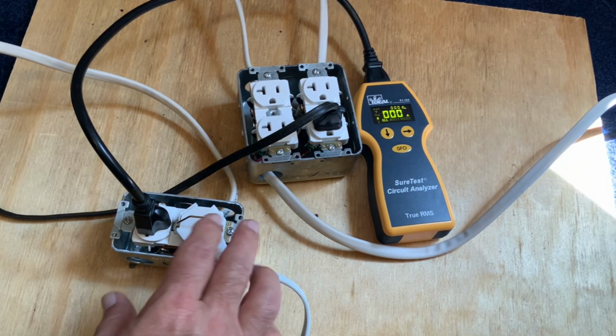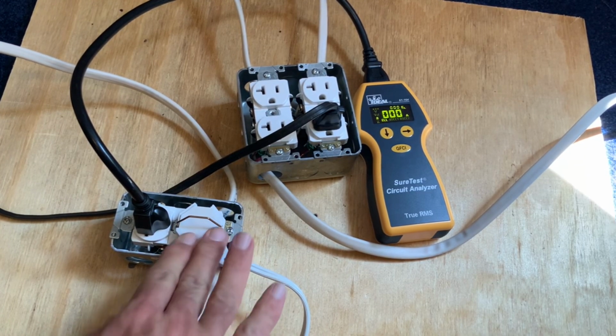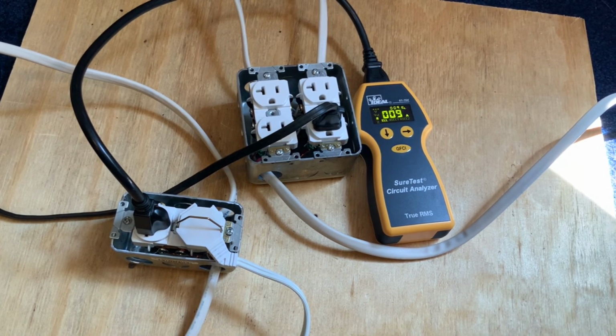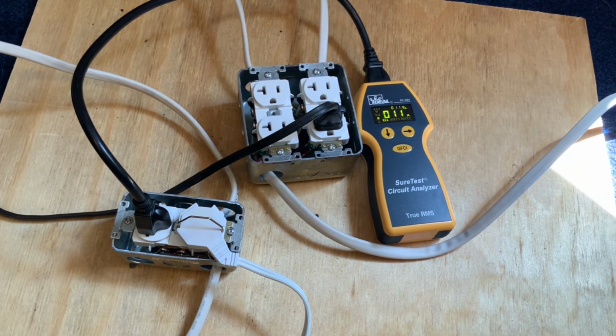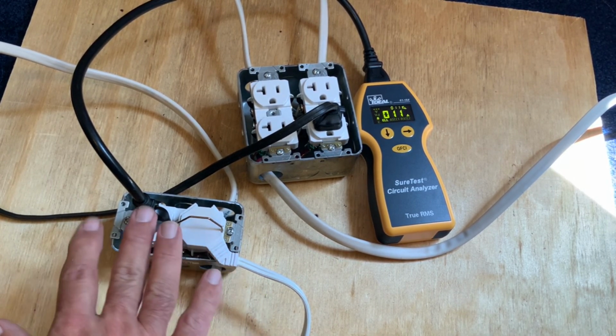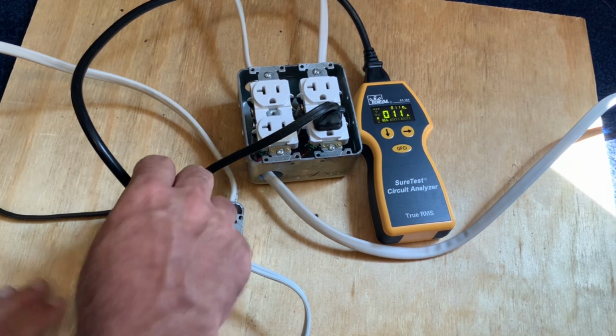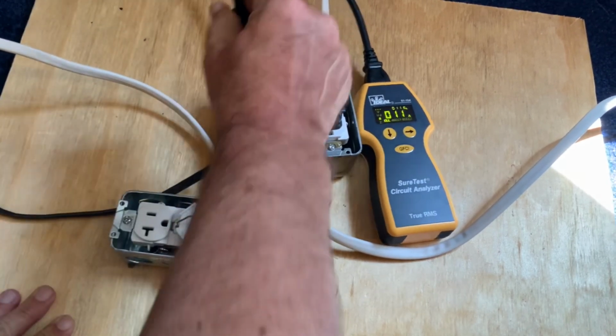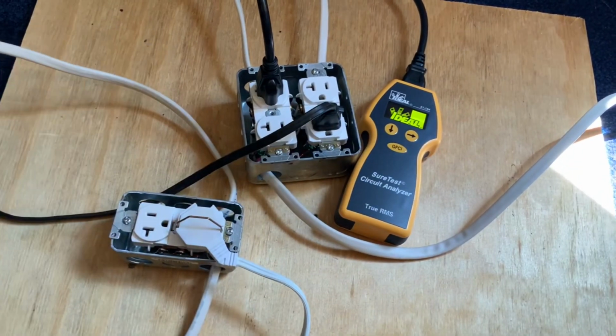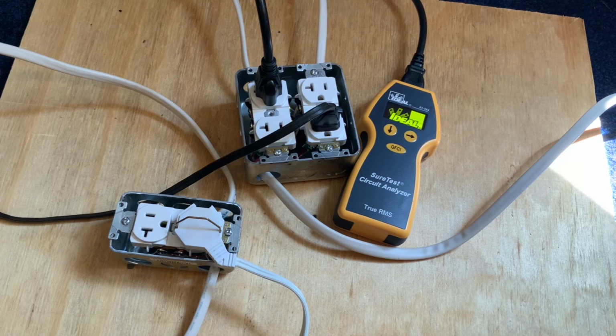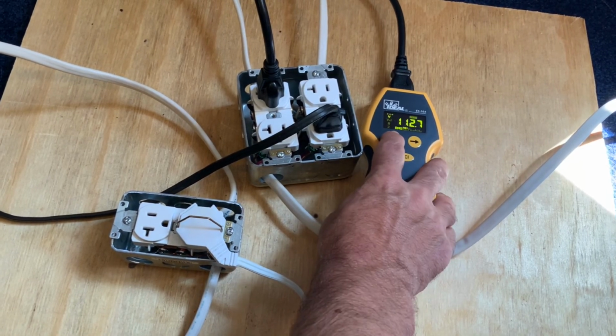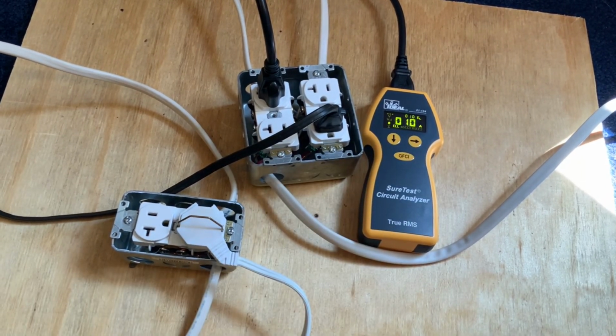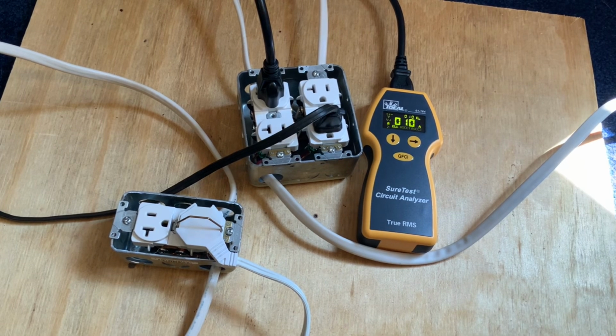So if I have my tester plugged into the same outlet as one of my heaters and I turn that heater on, I'm getting about 11 amps, which is really close to what is drawn up. It's about 11.5 amps. So it's pretty accurate with the load and the tester in the same outlet. So now let me just move the tester to this outlet so it's closer to the breaker, beyond that 90 feet of Romex that I showed you earlier. And if I look now, I'm showing 10 amps, so still pretty close, pretty accurate.